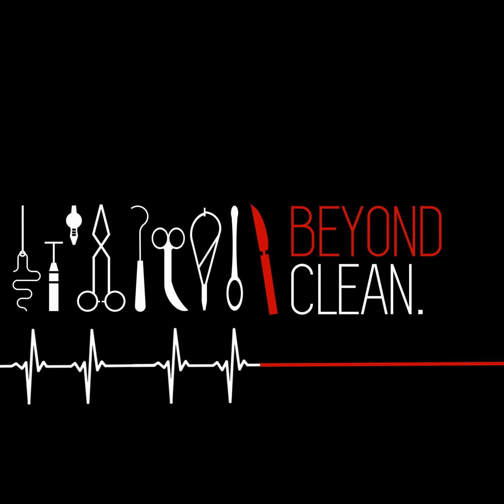Well, I think it may be the other way around, where the disinfection and the sterilization can have an impact on the colorant. But I think the outcome is the same, which is that most of what I'm concerned about is safety, is any chemistry that's going to be coming off a device. For example, if you start looking at some colored devices that are anodized, the anodization process really is just like oil and water that makes the color differences. And so that's not really a chemistry. It's more about light diffraction.